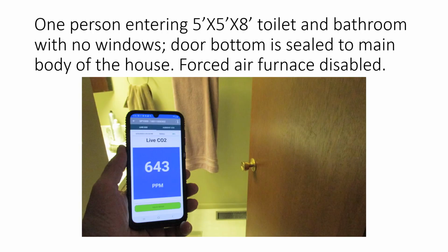Well, that one person, me, is going to enter a 5 foot by 5 foot by 8 foot high toilet and bathroom. There are no windows. The door bottom is sealed with a rug to make sure there's no other air getting into that room. The forced air furnace, as I said, is disabled. There's an exhaust fan, but it's turned off in that room, and the damper is closed on it. So at 643 parts per million, I enter the room.